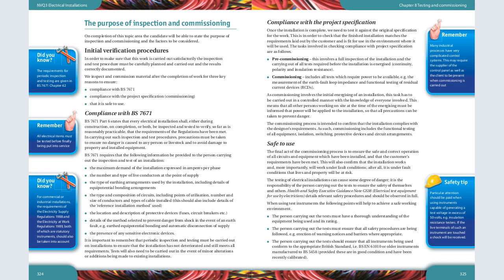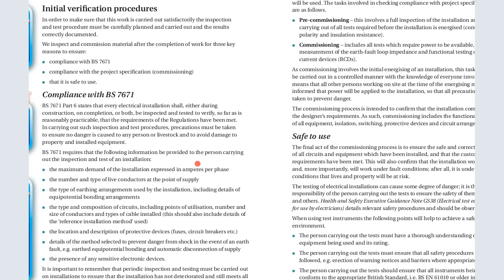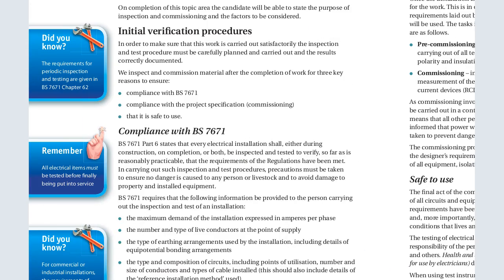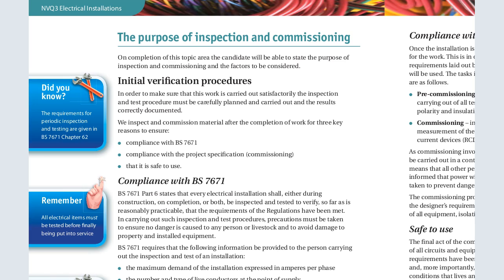I'll take you through the procedure of testing, what is needed during this testing, and the whole process of testing. So, the purpose of inspection and commissioning. Once an installation has been done, we need to inspect. Why do we need to inspect? Another vital thing: on completion of any installation, an inspection has to be done. This is the initial verification procedure, in order to make sure that the work is carried out satisfactorily. The inspection and test procedure must be carefully planned and carried out, and the results correctly documented.